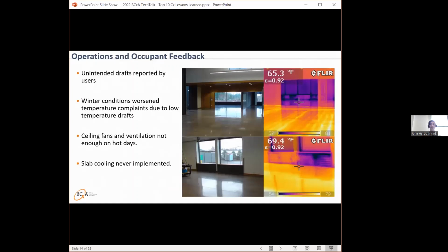This was after numerous occupant complaints. We had unintended drafts reported by users—cold drafts, we're talking 55 degrees, or 50 to 55 degrees at your legs when you're in a classroom, which is extremely uncomfortable, just like 55 degrees dropping on the back of your neck is uncomfortable. Winter conditions were way worse, with infiltration being even colder.